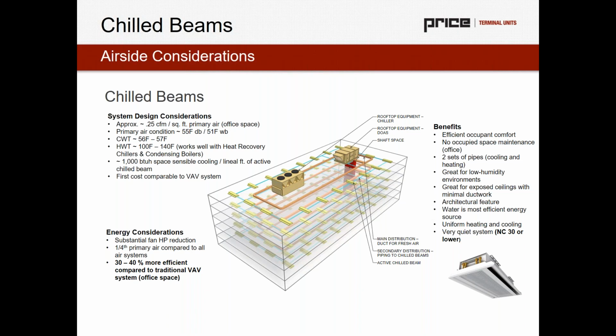When we compare this kind of system to a traditional VAV system, we're seeing substantial fan horsepower reduction. We're seeing a quarter of the total primary air supplied, just because of that dedicated outdoor air system methodology. And then we're seeing a 30 to 40% more efficient total system in comparison to traditional VAV. The other excellent thing, which we'll touch on more with chilled beams, is that they are a very, very quiet system. We're generally seeing a system design of NC 30 or lower with this kind of space.